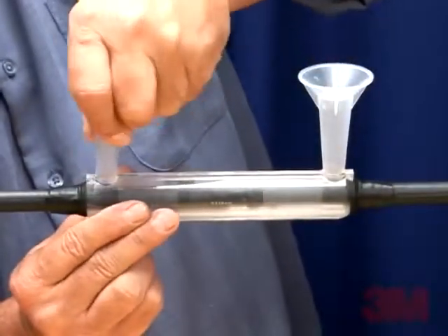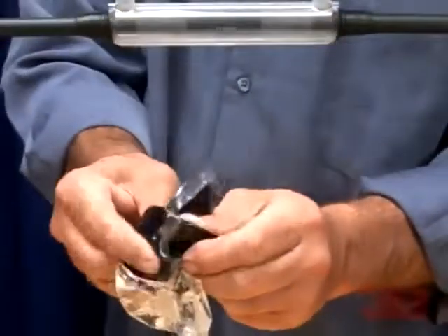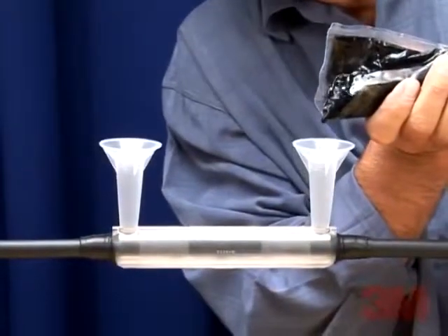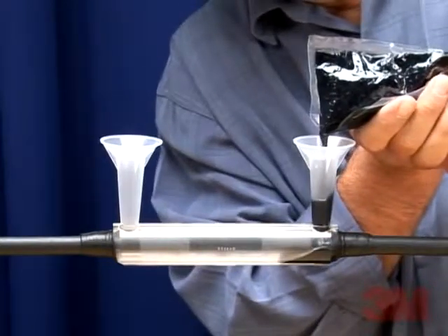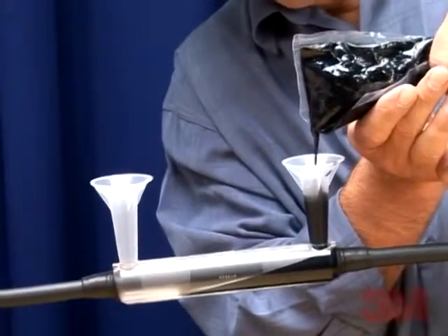Step 4: Put the pouring spouts in the holes. Make sure the splice position is level. Mix the resin thoroughly according to the instructions on the resin package. Pour the resin immediately after mixing. Fill only through one spout until both spouts are completely filled. When the resin has solidified and cooled, the splice may be put into service.